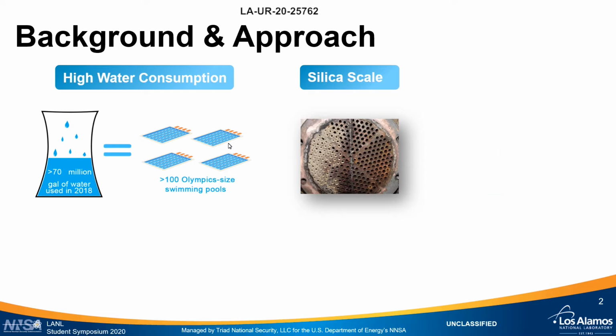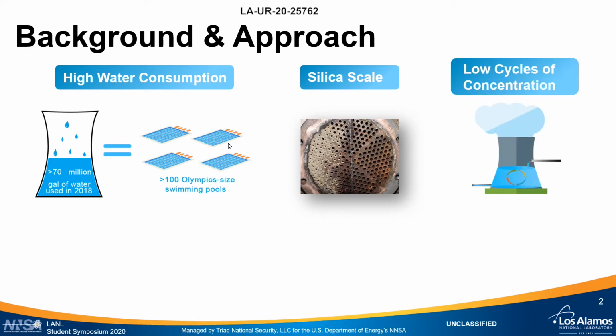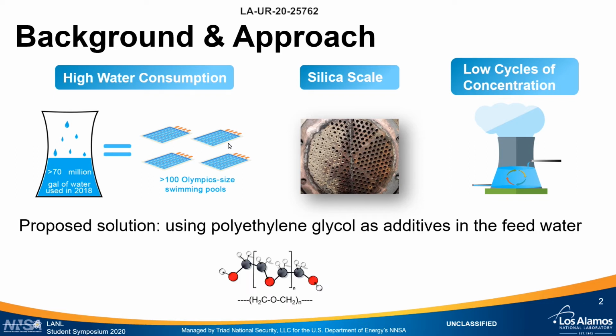Currently the cooling towers at LANL can only run up to 2 to 2.5 cycles of concentration, meaning at least 40% of the water in the cooling towers has to be discharged in one cycle. This is not ideal; the ideal efficiency is 4 to 5 cycles of concentration. In an attempt to solve this problem, we are proposing to use polyethylene glycols as green additives in the feed water.